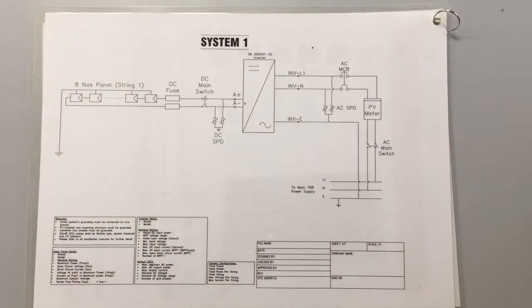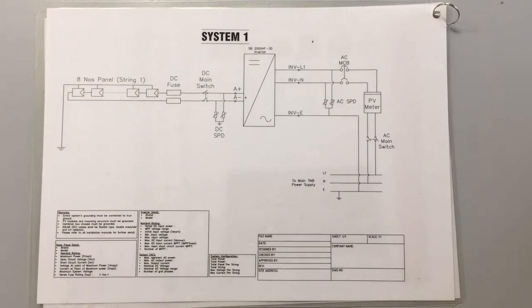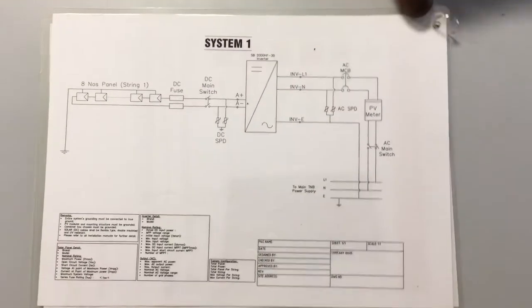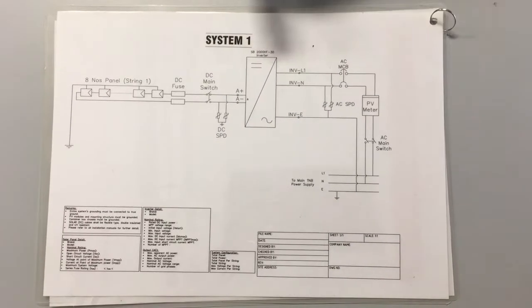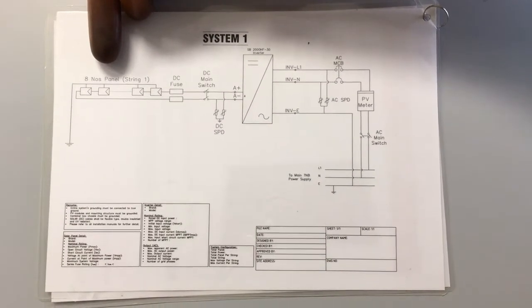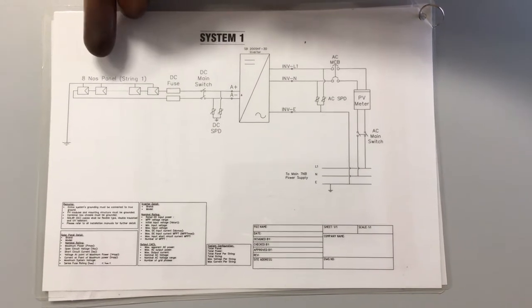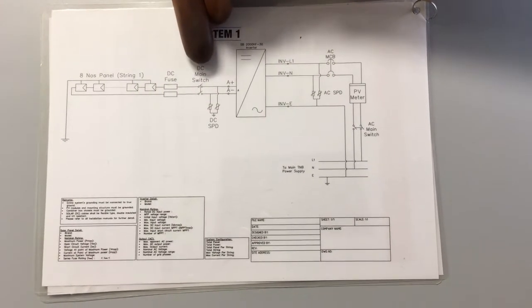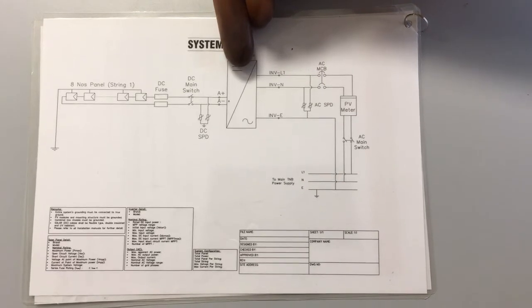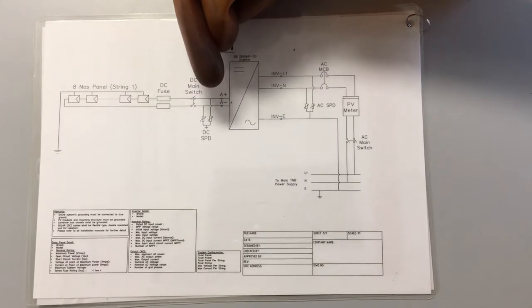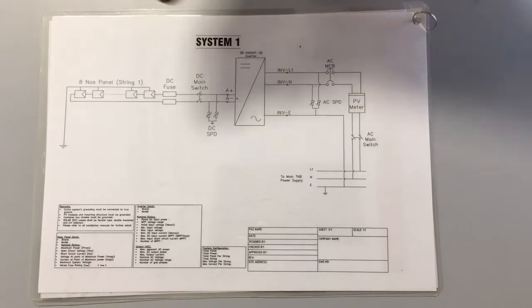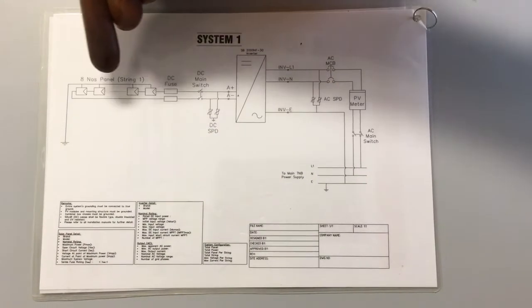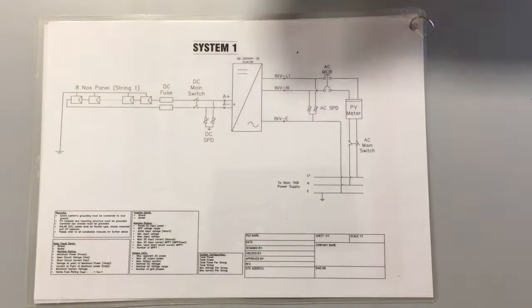This is the schematic diagram for the system that we want to assess. We move from the left to the right. The center is the inverter. We have 8 panels forming one string, and from the PV modules, the string goes into the DC fuse, then into the main switch, and then from the main switch to the inverter input. In between we have a DC SPD. If you recall, SPD is a surge protective device. Its function is to protect the inverter from lightning surge. If there is a lightning strike at the module, the voltage will travel along this line and be captured by the DC SPD.